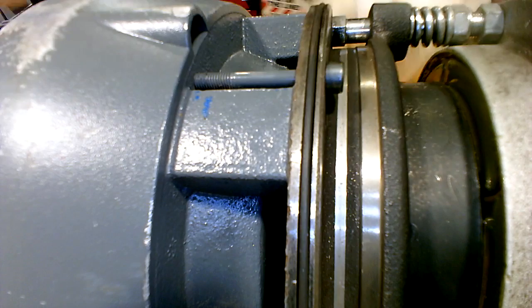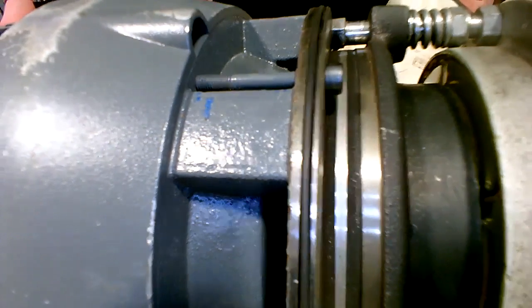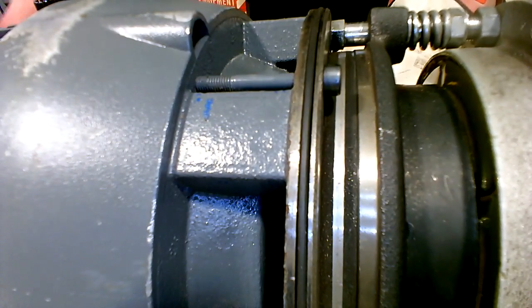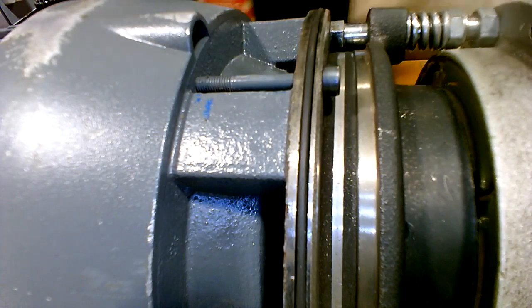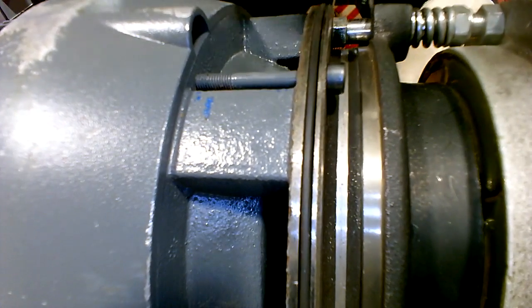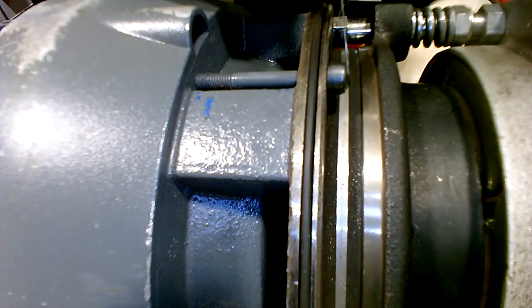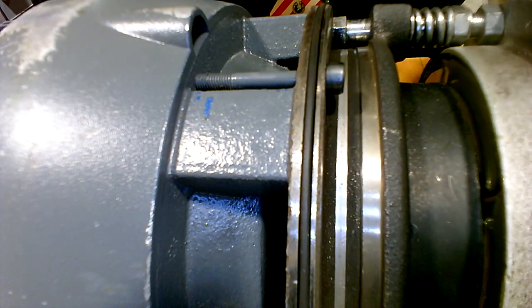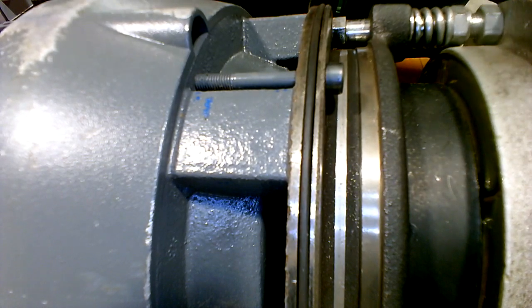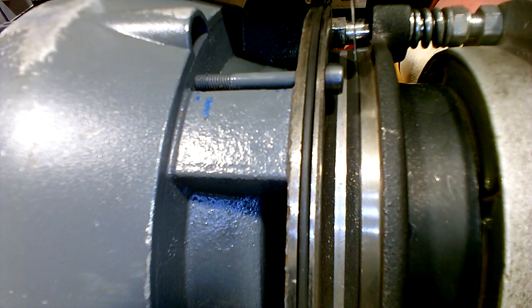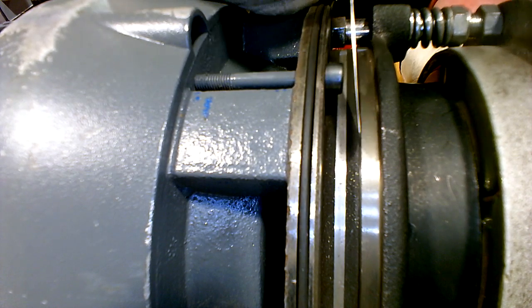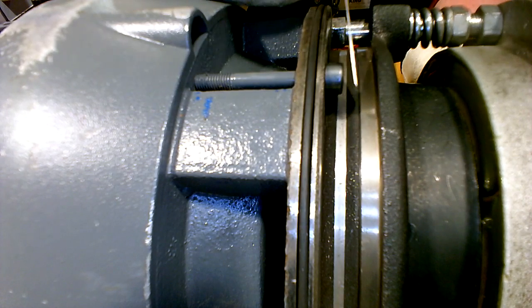If we take the feeler gauge, where's that feeler gauge at? If we take the feeler gauge and get in there, right now you cannot get it in, because look, the coil is released and now it's engaged. So you can't get the feeler gauge in there now. There's no gap in there whatsoever.